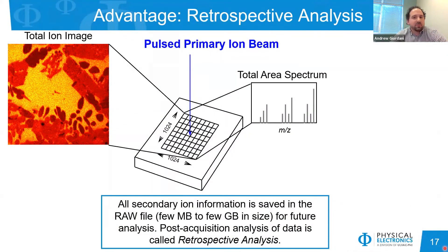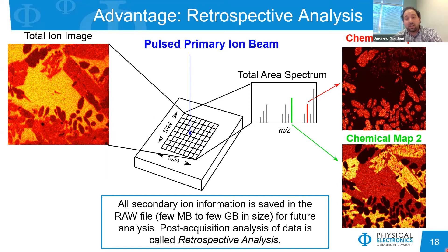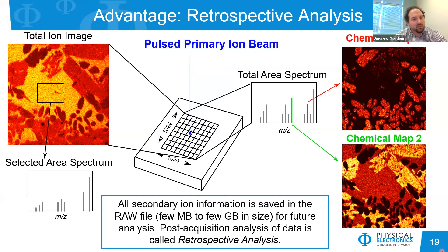Retrospective analysis is another advantage of TOF-SIMS depth profiling. As the primary ion beam pulses over the sample, a mass spectrum is generated at every XY pixel and stored into the computer. You can look at the full mass spectrum integrated over the whole area and generate chemical maps of any mass-to-charge ratio. You can work from the total ion image to look at specific regions of interest and generate mass spectra from those areas. Since all information is stored at each depth, you can reconstruct and examine images and spectra at different depths throughout the sample.